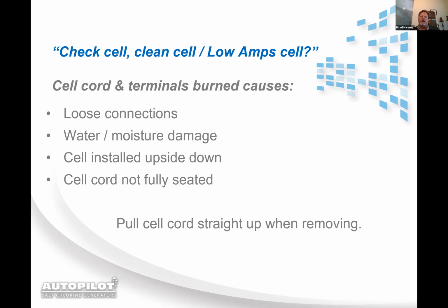wiggling it back and forth. They are tight, so it's okay to wiggle it a little bit. Just don't get overly aggressive, because those connectors inside the cell cord, they are not a complete solid connection. There is a gap that runs the full length of that copper brass connector. So if you're wiggling it back and forth aggressively, you could spread them out and create a gap and create an issue. Also, don't ever pull up on the cell cord itself. You can cause it to lose connection there.